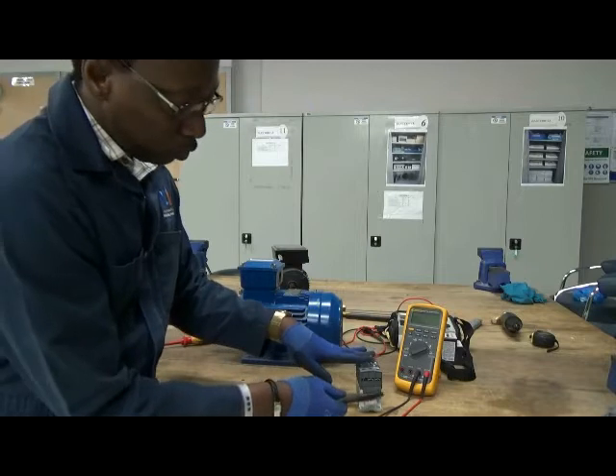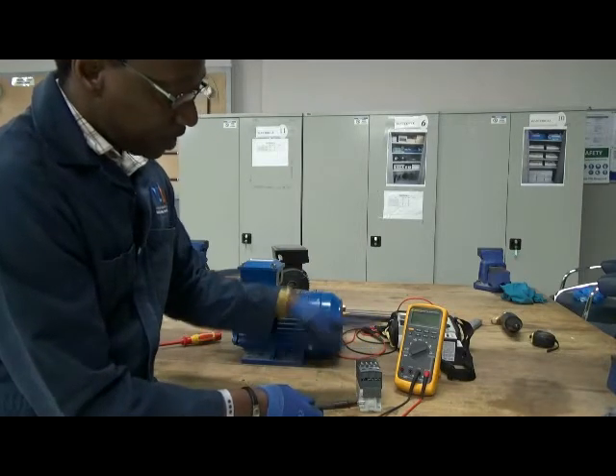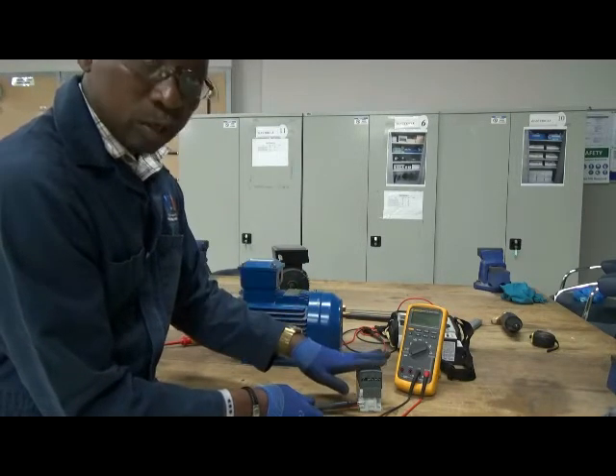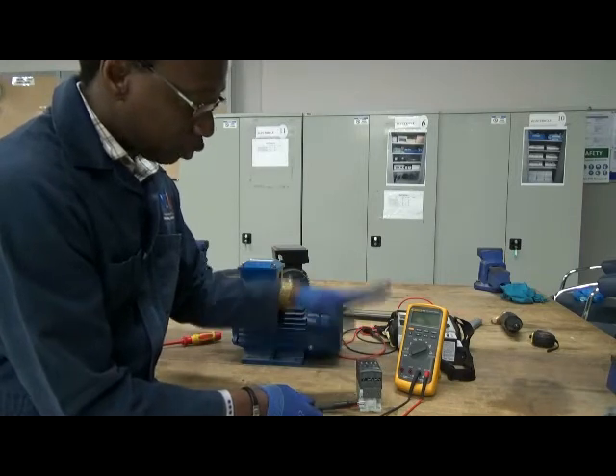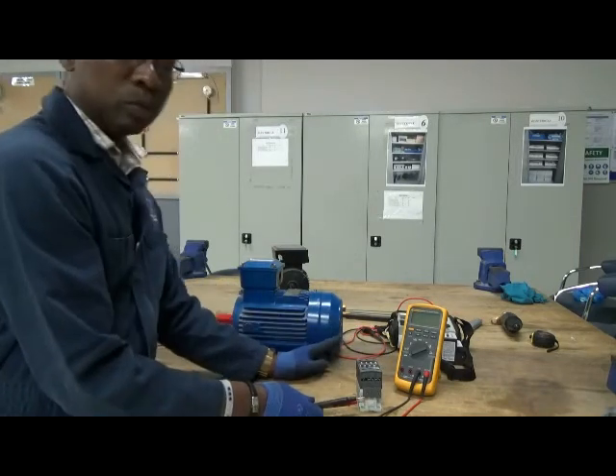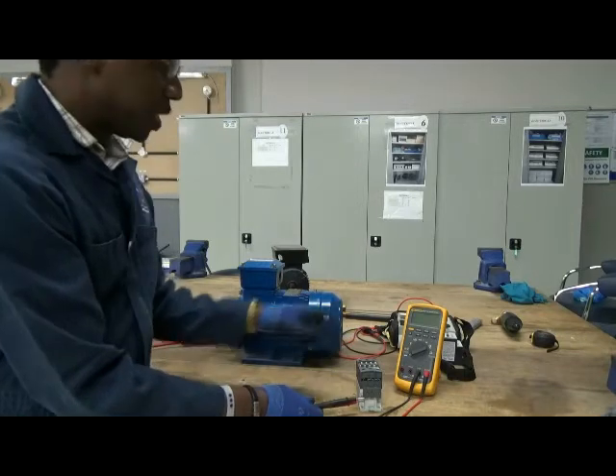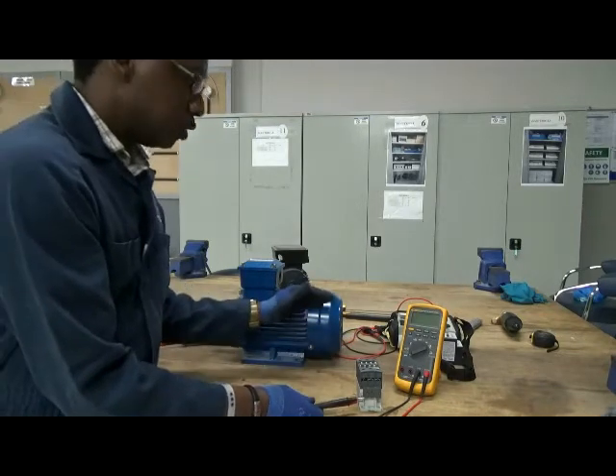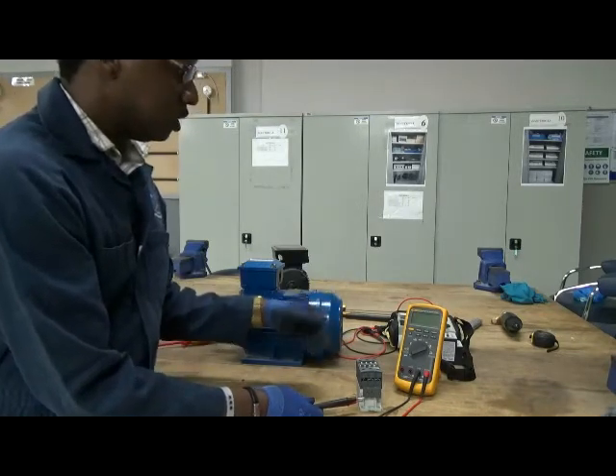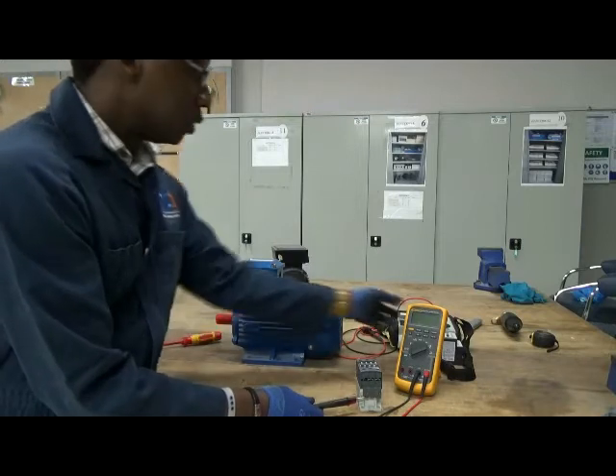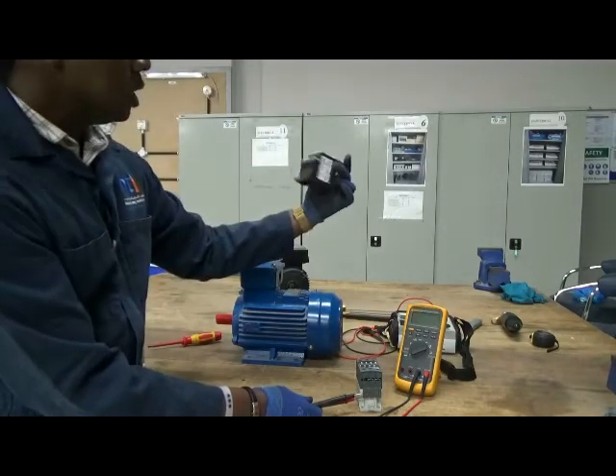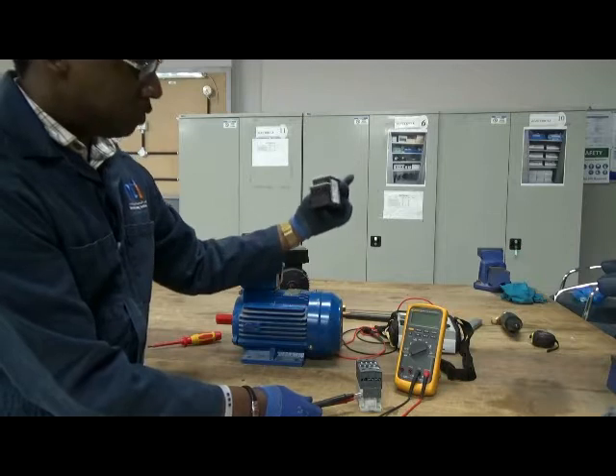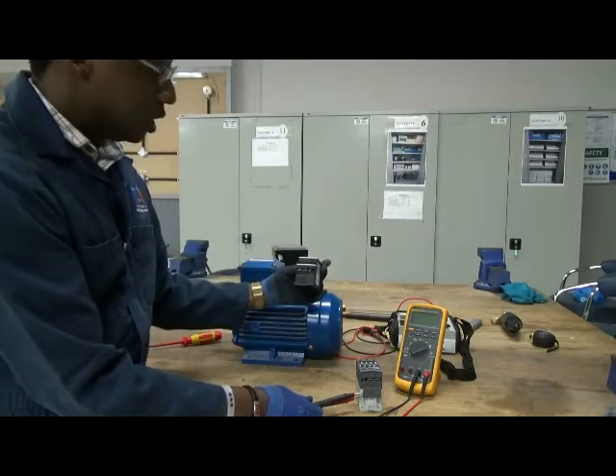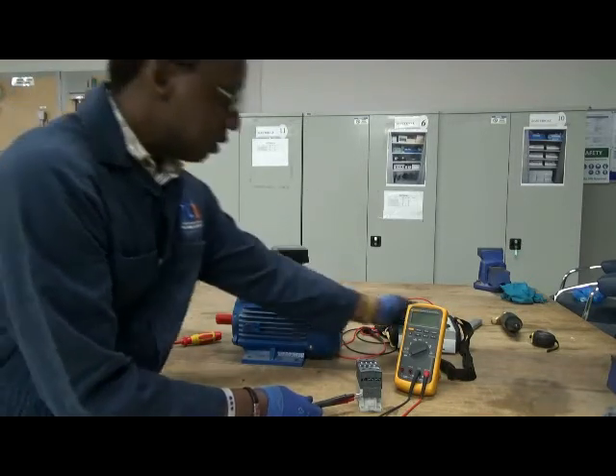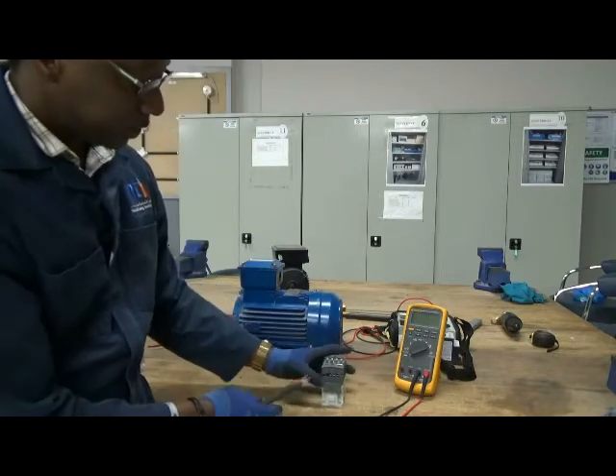But the moment you energize the coil, the contacts inside close, and when they've closed, power will be able to pass through. And it can pass through to wherever you want, either to the motor or in most cases it will have to go first to what we call an overload relay. This is an overload relay. This is an overload relay used to protect the motor against overloads. Right, but let's talk about the contactor first.